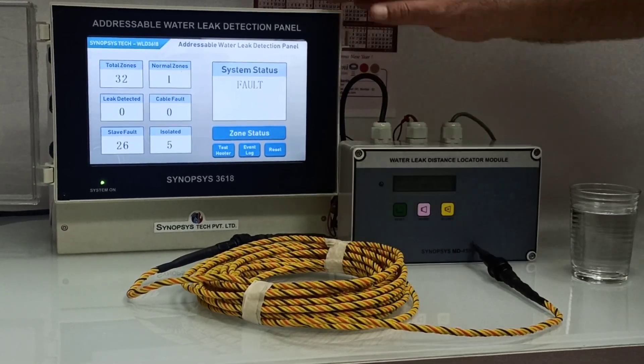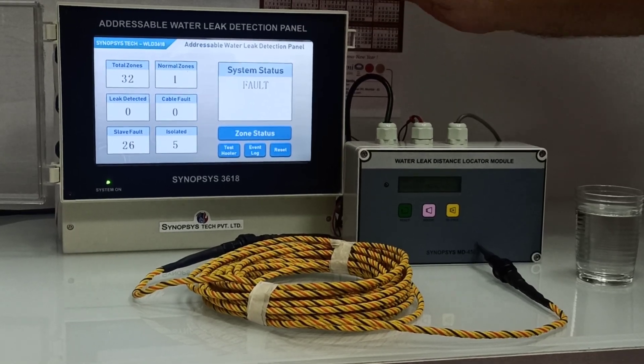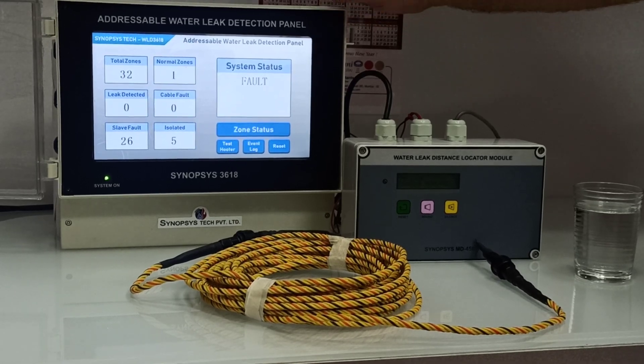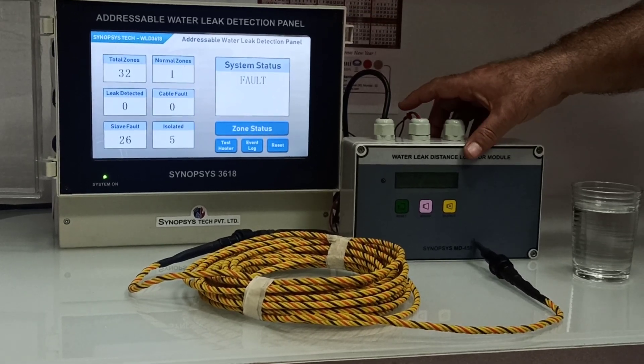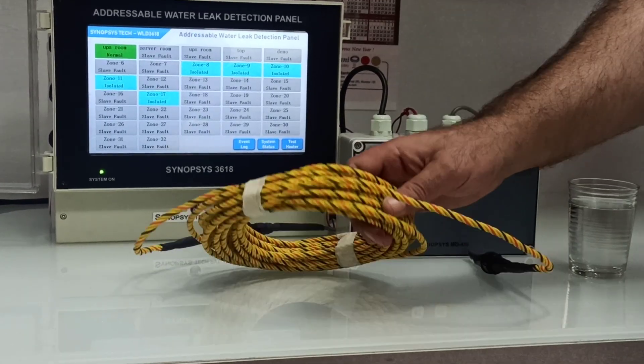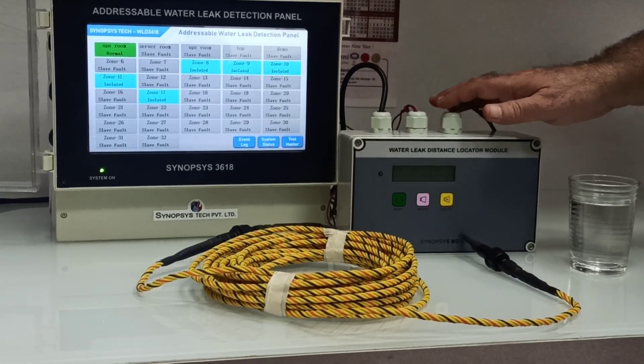We have a main panel which can take 32 slave modules. This panel can take from 2 to 32 modules. Each module can take 150 meters of water leak cable, so the total water leak cable in a system will be around 4800 meters.